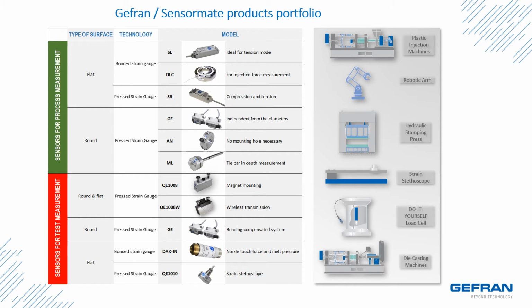We also have certain types of sensors that are round for specific areas on some of the applications we discussed that you want to measure compression or tension for as well. And then the flat and round series for more of the tie bar measurement type applications. They use a pressed strain gauge type of technology. The actual strain gauge that we use is very accurate and does a good job in terms of feeding that measurement back to our system.